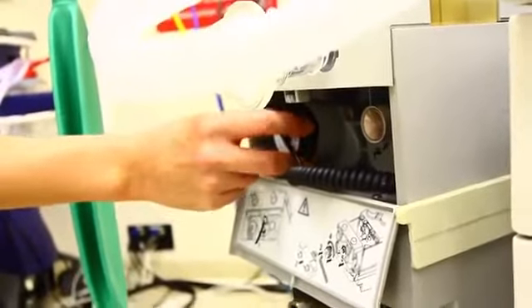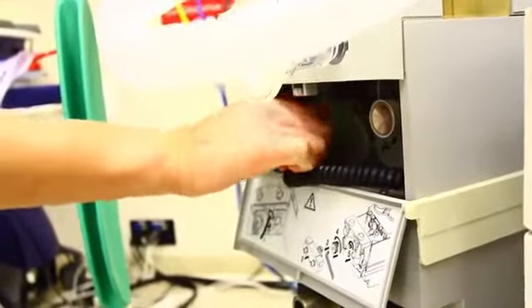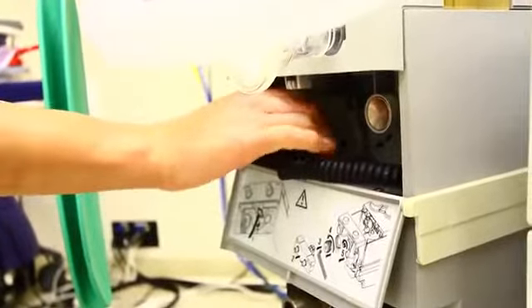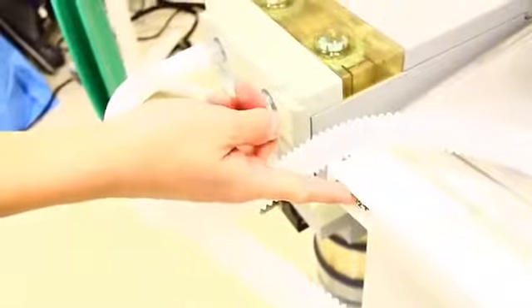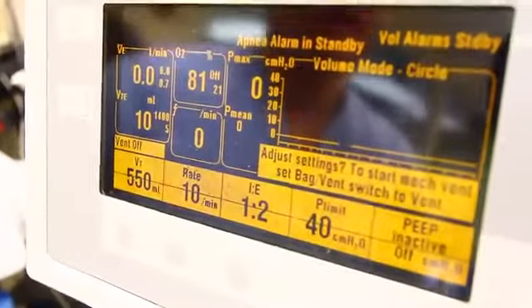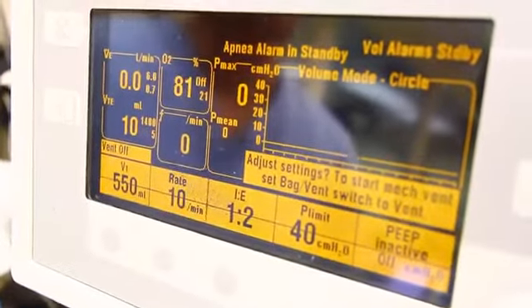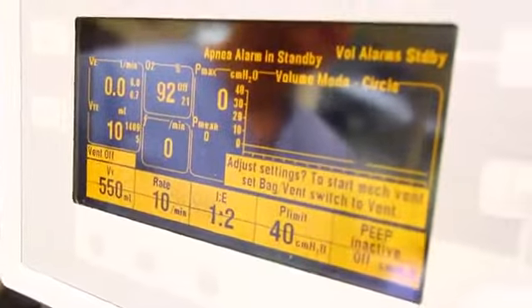Now you want to reinstall the oxygen sensor, insert it and turn it clockwise, then close the door. Activate the oxygen flush valve, and you want to verify that the oxygen level goes above 90%.